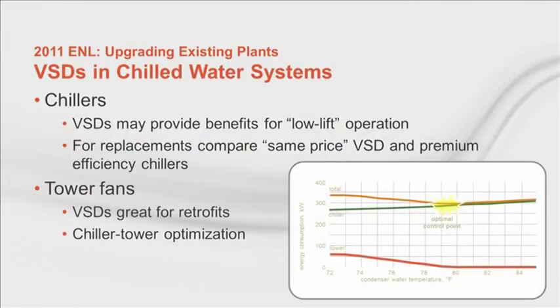Cooling tower fans are often a great retrofit application for VFDs. From a chilled water pump standpoint, there is low-hanging fruit for applying VSDs, especially in constant flow systems that have low delta Ts and high flow rates. But what about the condenser water pump? Shall we put a drive on that?